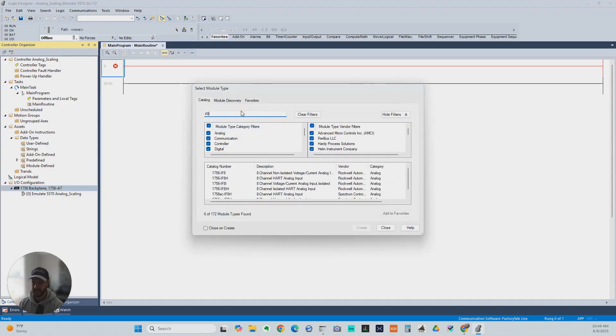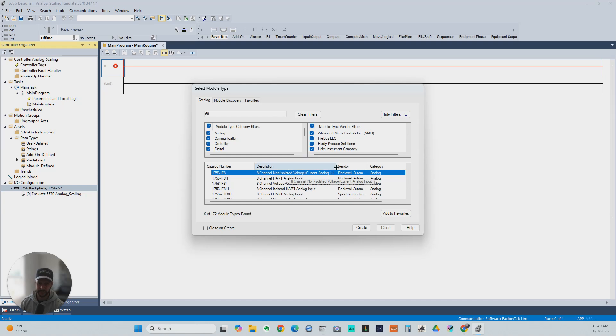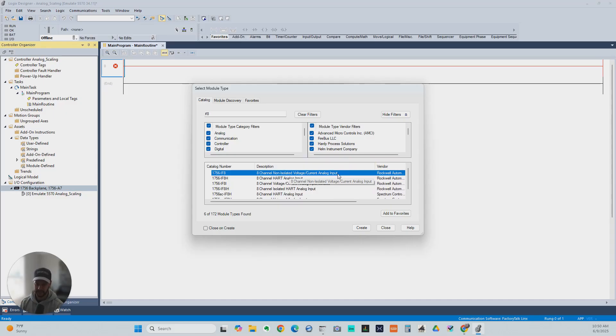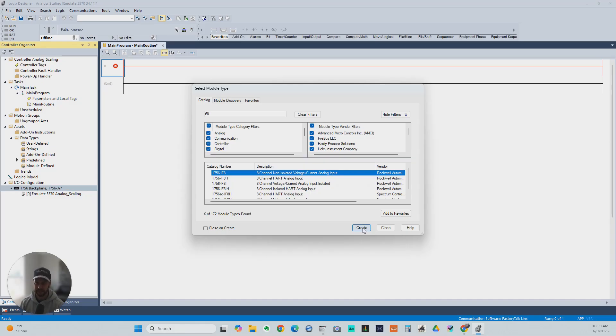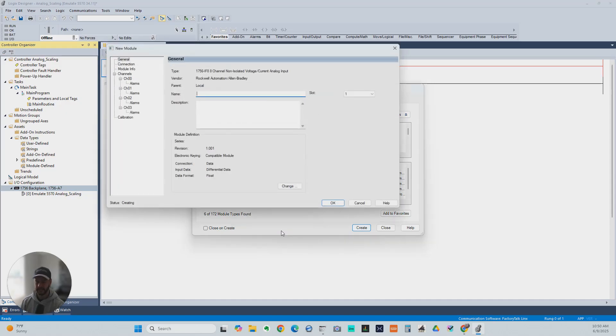We're going to go for the IF8, which is an 8-channel non-isolated voltage or current analog input module. This can read voltage inputs like a 0 to 10 volt signal or a 4 to 20 milliamp, which would be the current signal. It can use either type signal. So we're going to add that.